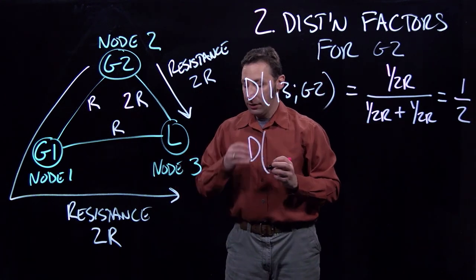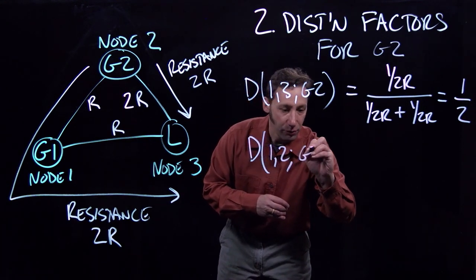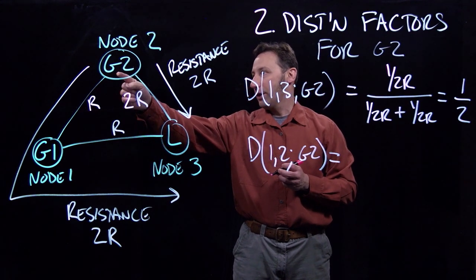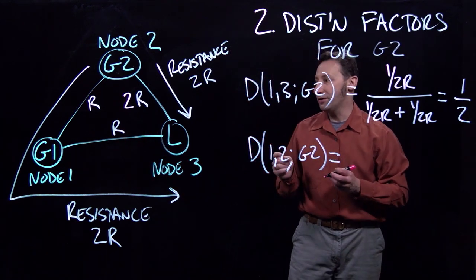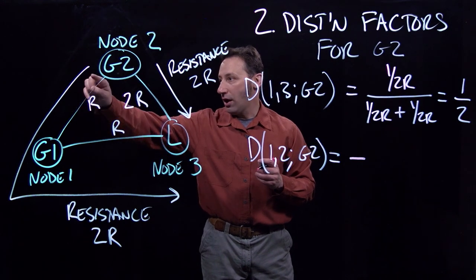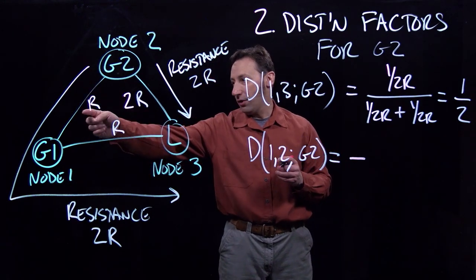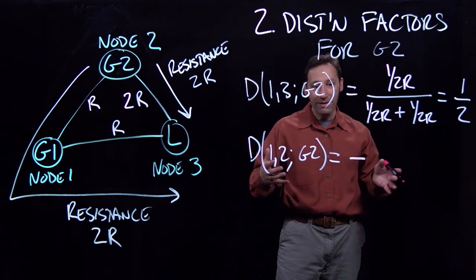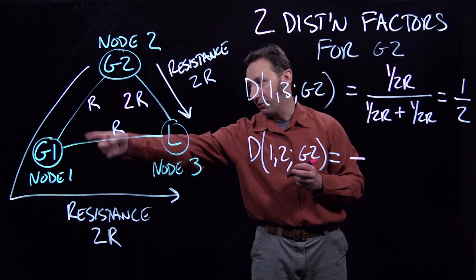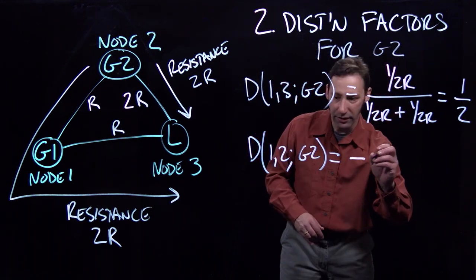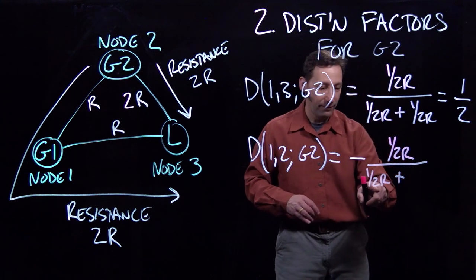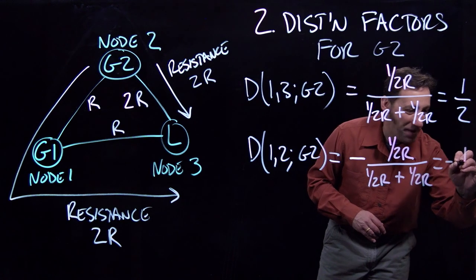The distribution factor on line 1 to 2 from G2 requires remembering that power going from node 2 to node 1 is in the negative direction, so there's a negative sign in front of the distribution factor. Both lines making up the indirect path have the same magnitude distribution factor. In the numerator we have 1 over 2R, and in the denominator 1 over 2R plus 1 over 2R, giving us negative one half.